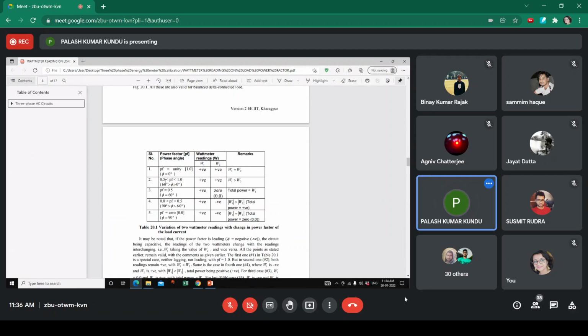When the power factor lies between 0.5 and unity, that is the phase angle is between 0 degrees and 60 degrees, both wattmeters will read positive, but the magnitude of W1 will be greater than W2 when the power factor falls in this range. When the power factor is exactly 0.5, that is the phase angle is 60 degrees, one wattmeter reading will vanish. It will be 0, and the whole power will be measured by the other wattmeter, that is W1, and the total power will be equal to W1.